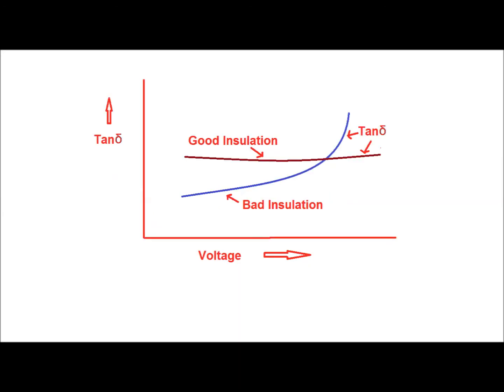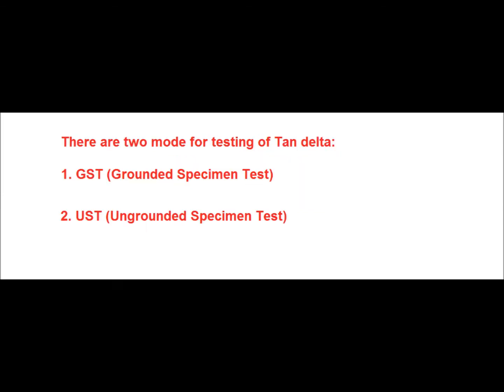In this diagram, an example has been shown for good and bad insulation. In the case of good insulation, when the applied voltage increases, the tan delta values of the insulation remain more or less the same. But in the case of bad insulation, with the increase of applied voltage, the tan delta value increases. Basically there are two modes for testing of tan delta: GST, that is grounded specimen test, and UST, that is ungrounded specimen test.